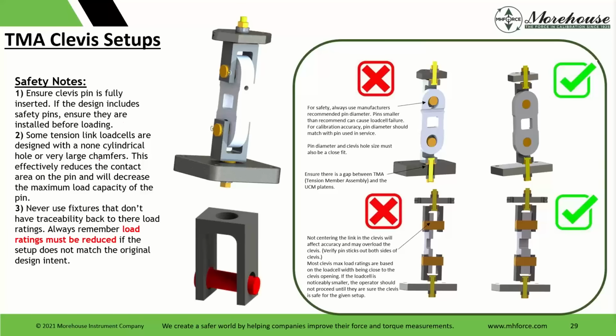Some tension link load cells are designed with a non-cylindrical hole or very large chamfers. This effectively reduces the contact area on the pin and will decrease the maximum load capacity of the pin. And then never use fixtures that don't have traceability back to their load ratings. Always remember the load ratings must be reduced if the setup does not match the original design intent.